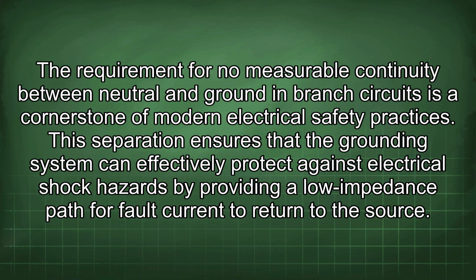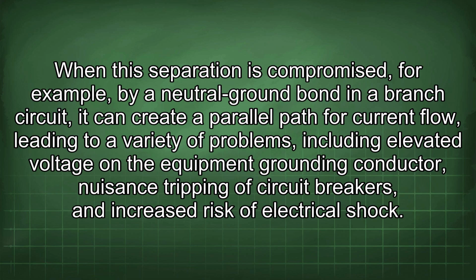The requirement for no measurable continuity between neutral and ground in branch circuits is a cornerstone of modern electrical safety practices. This separation ensures that the grounding system can effectively protect against electrical shock hazards by providing a low impedance path for fault current to return to the source. When this separation is compromised, for example, by a neutral-ground bond in a branch circuit, it can create a parallel path for current flow, leading to a variety of problems, including elevated voltage on the equipment grounding conductor, nuisance tripping of circuit breakers, and increased risk of electrical shock.